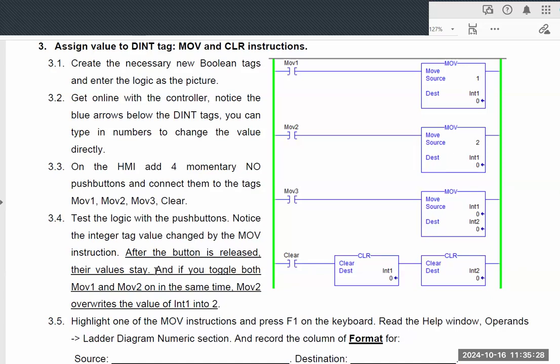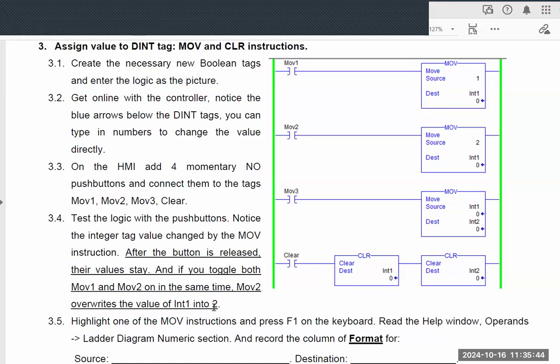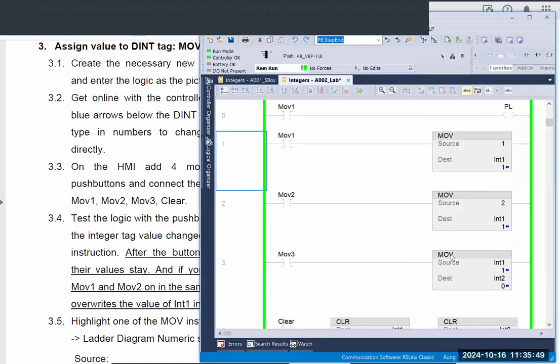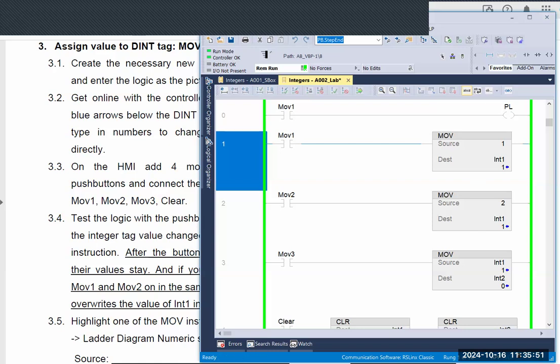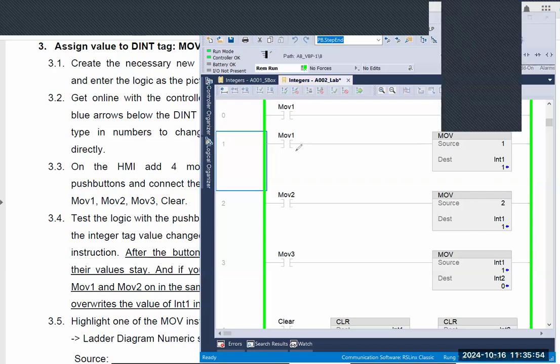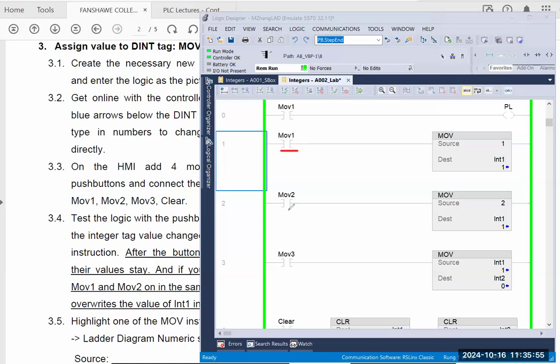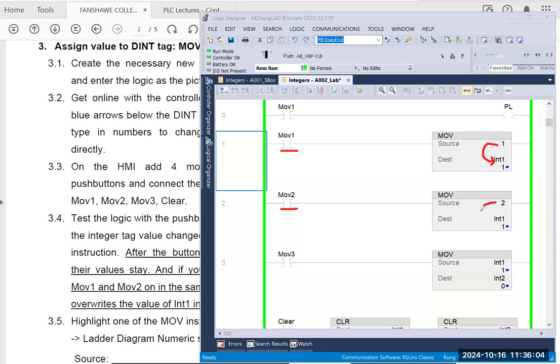Second part I want you to observe is that if you toggle both MOV1 and MOV2 in the same time, MOV2 overrides the value of integer 1 into 2. What we mean by that is, if you look at the logic, in the same time, with the trigger MOV1, you copy the value 1 into INT1, but with the MOV2, you override the value 2 into the same destination, INT1.